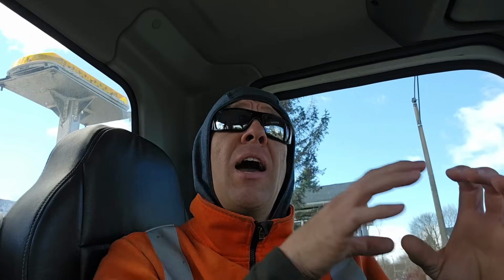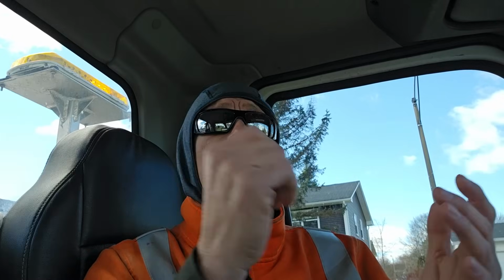If I go in with an idea of what switches are my protection points, I communicate with them and they all line up, I feel much more comfortable than just the dispatcher giving me my normal opens, going off and tagging them. So it's actually a very important step in the field to make sure you fully understand your work zone rather than just relying on someone else. It's a good 2-step authentication to your work permit, for lack of better words.